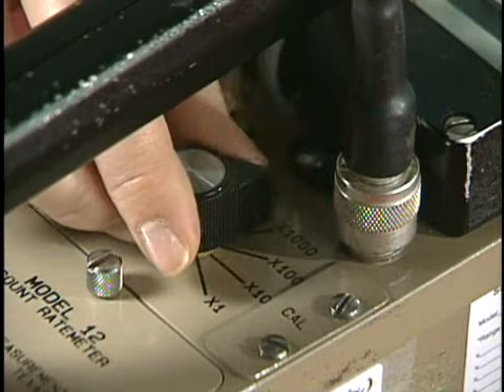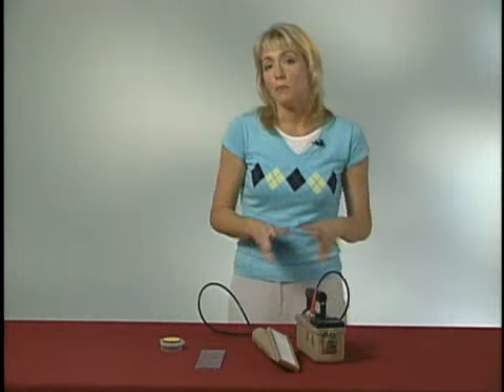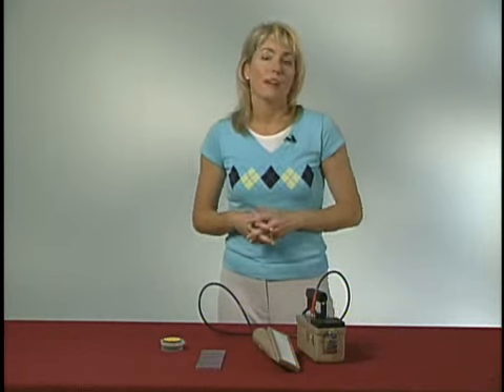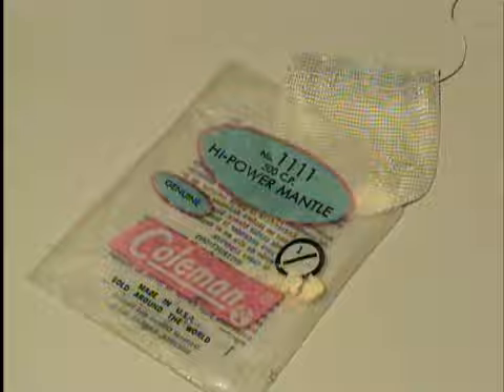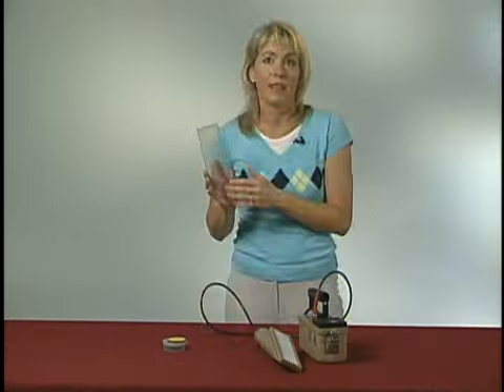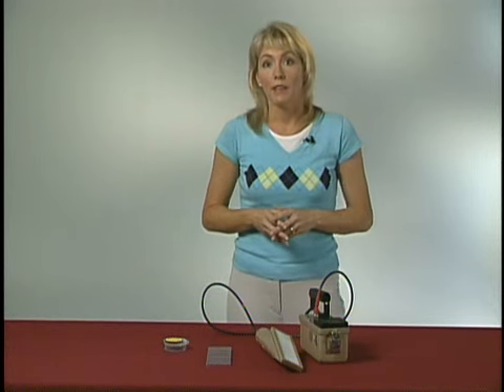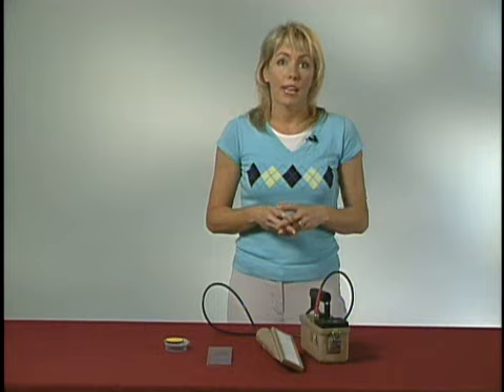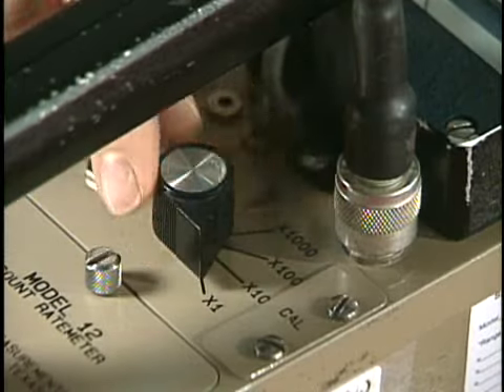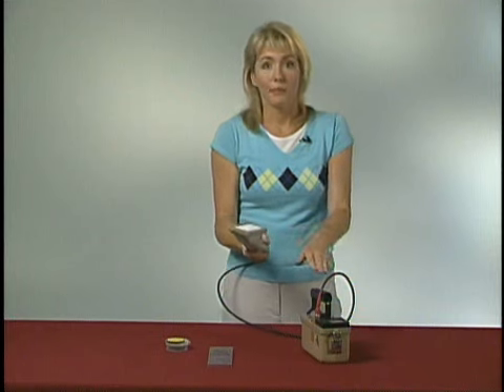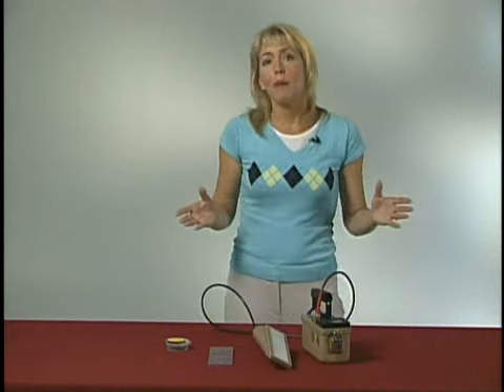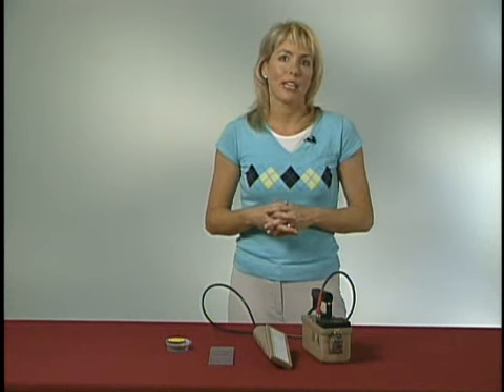Next, rotate the knob to the appropriate scale available and determine the instrument's response to a check source. As I mentioned before, a thorium-containing gas lantern mantle or a plastic button check source can be used here. When checking the alpha scintillator, be sure to remove the plastic cover from the probe, assuming that it has one. And if the check source is in a bag, remove it, because alpha particles cannot even get through a piece of paper. The next step is to check background. Turn the meter on in an area where elevated radiation levels are not expected. And using the most sensitive scale, record the reading on the meter. As mentioned before, a typical background for an alpha scintillator would be 0 to 2 counts per minute.